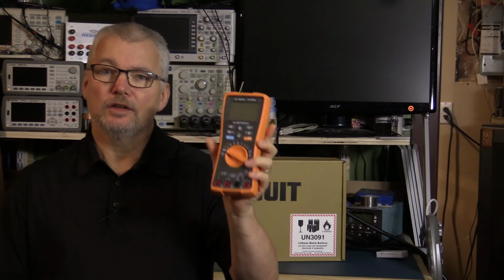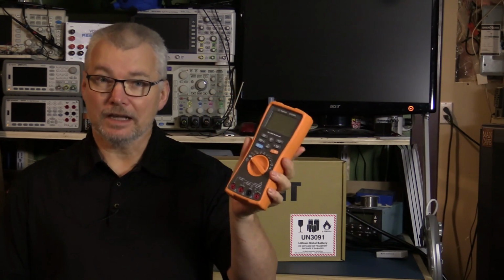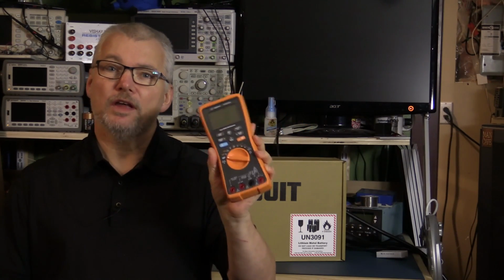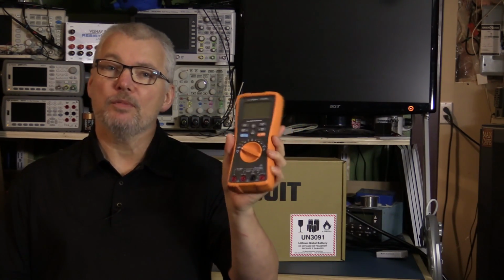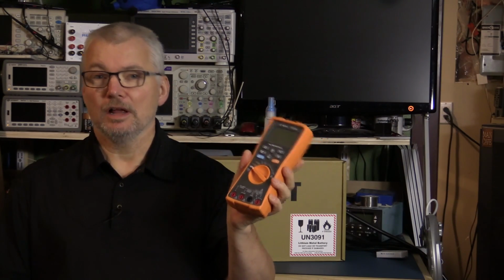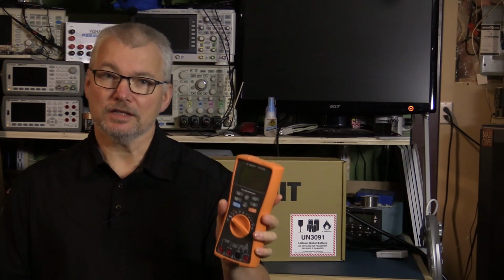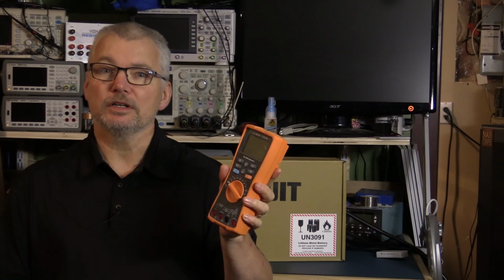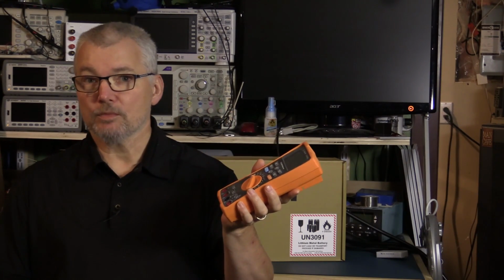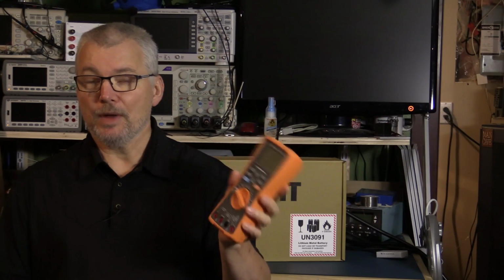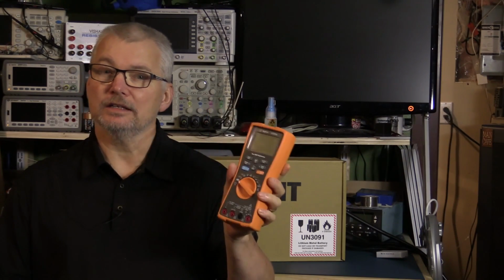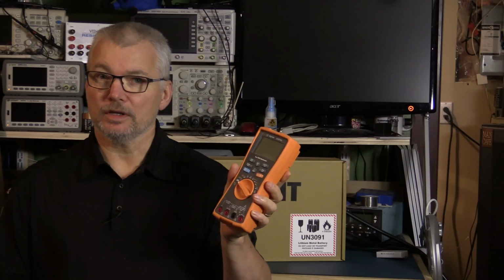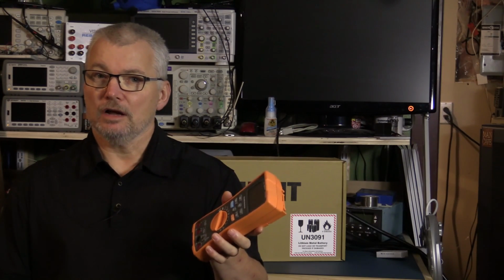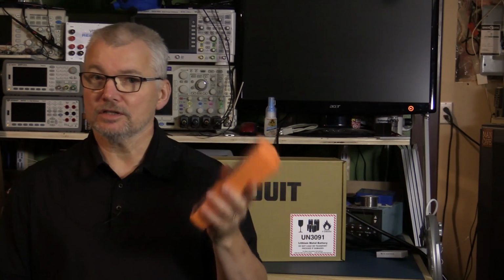On top of that, you have to verify or validate that your multimeter is reading properly before you test the equipment. Then you go to the equipment, do the test, and you're typically looking for 0 volts to be present. Then you go back and validate your meter again to make sure it's still functioning properly. And that's all before you can even start working on the cabinet or whatever piece of equipment you're needing to do maintenance or installations on.